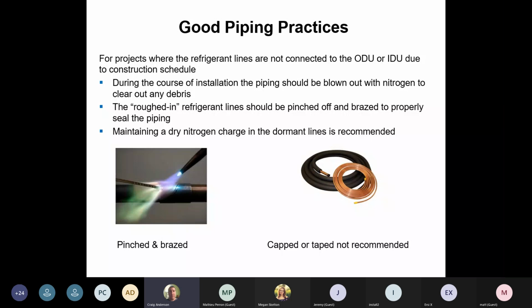So just be mindful when you're running your lines, crimp them off. We're talking about pinching them off and brazing them in here. If you don't have your tools to braze it, at least pinch it off. That is going to solve a lot of the problems down the road. The install guy gets back, throws the air conditioner on. We have no idea what we've put in that line. So just pinch it off. Just be mindful if you're running the line before that air conditioner is going in.